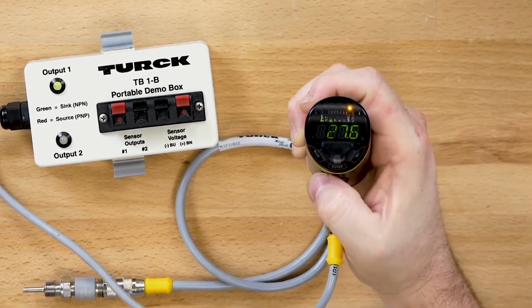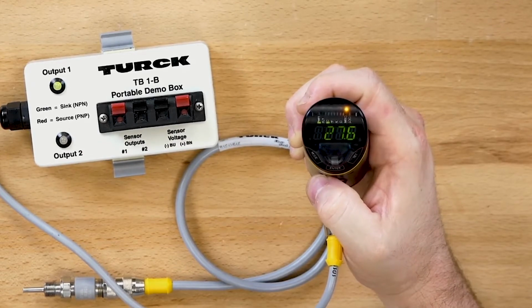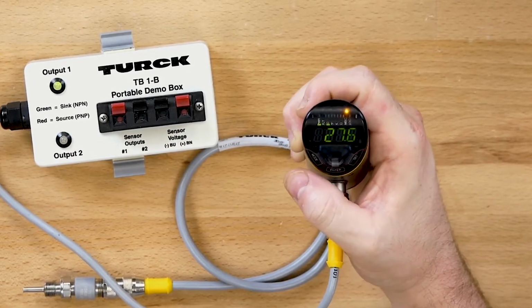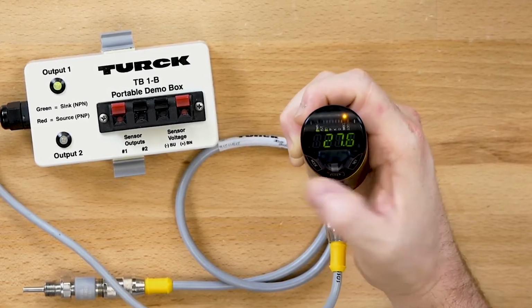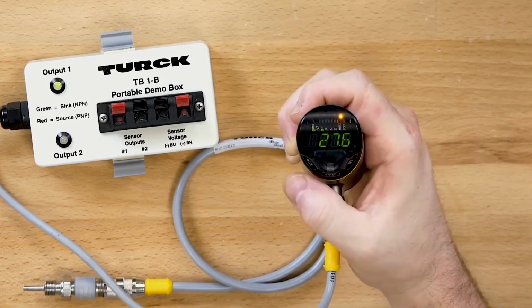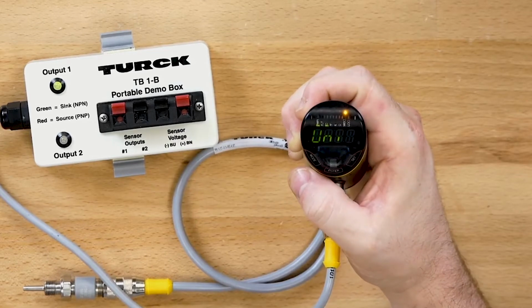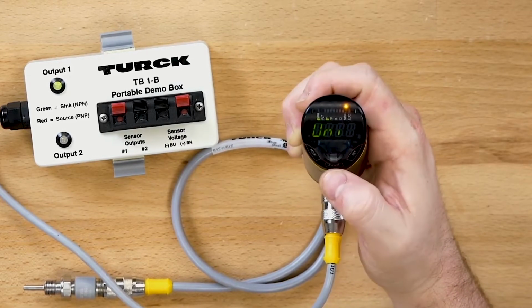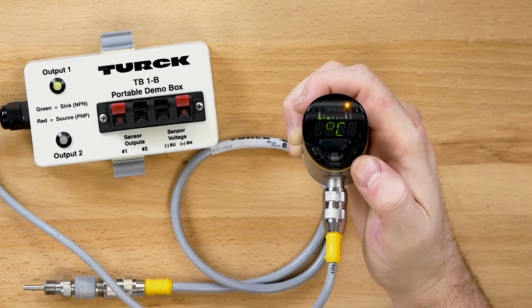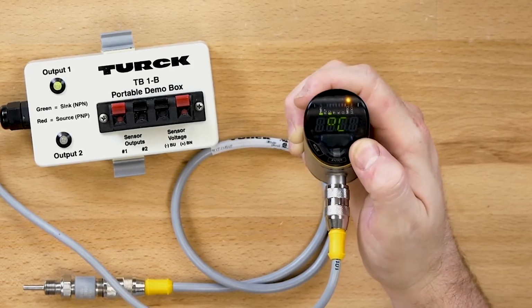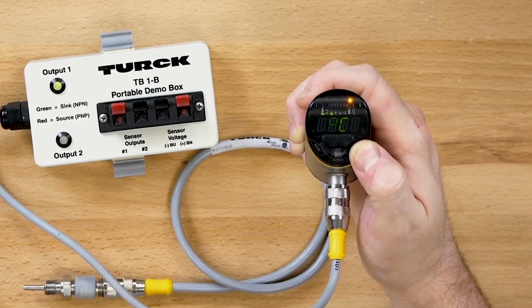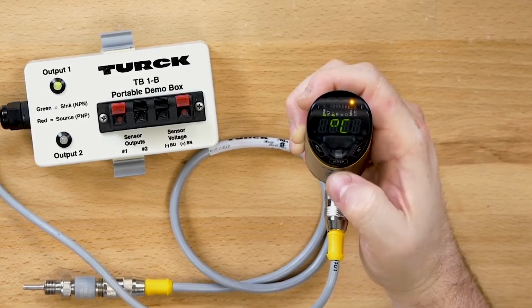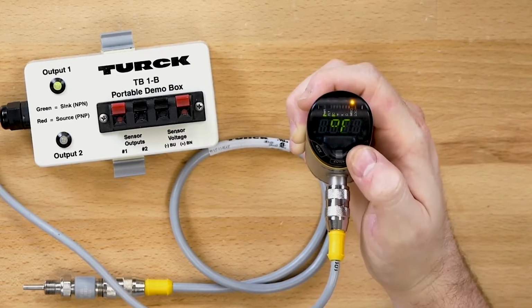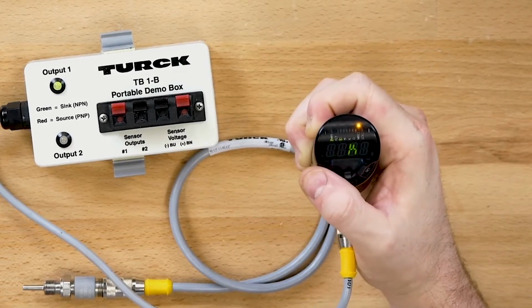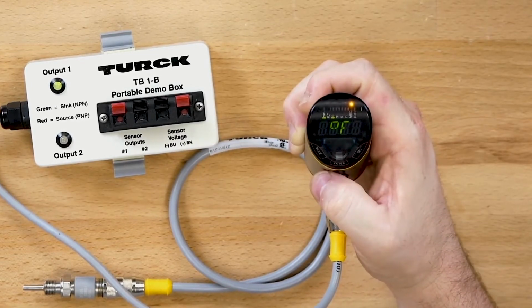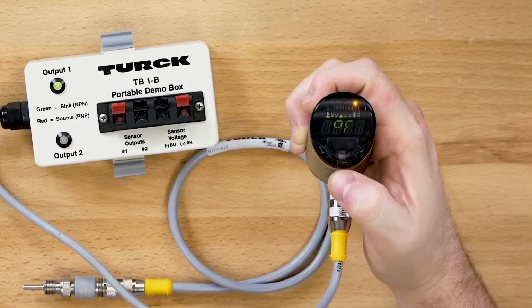With the TS Plus unlocked, let's first set the desired temperature units to degrees Fahrenheit. You can do this by navigating the menu with the Mode and Set capacitive touchpads. Once you get units displayed, abbreviated by UNI, click Enter, and then hold the Set button for 3 seconds until the screen stops blinking. You can then use the Mode and Set buttons to navigate various units of temperature until arriving at degrees Fahrenheit. Click Enter to set the units.